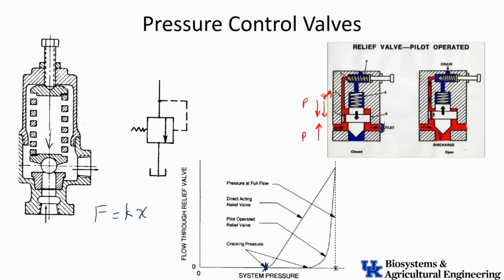Okay, again, this is a really small direct acting relief valve, just like the big one over here that we just looked at a minute ago. It's going to push this open, and some flow will start to go through it and out what we call a drain. So we have a little line here that we have to port back to the tank at some point. But we've got a little bit of flow sneaking out through there.